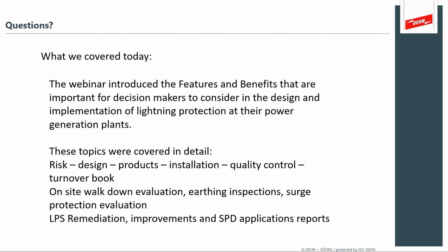And then, of course, if these tall structures are higher than 60 meters in height, we can generally do an air termination system design that would protect the upper part. The standard says the topmost 20% of the height of these structures, and make sure that especially the points and corners and edges of this tall structure are protected should a strike come from above. But the risk is generally lower for the percentage of flashes that we can expect coming from the sides. In the case of these power generating facilities, the stacks are not generally higher than 60 meters. And if they are, we will do a protection scheme that would address the assessed risk that we see there.